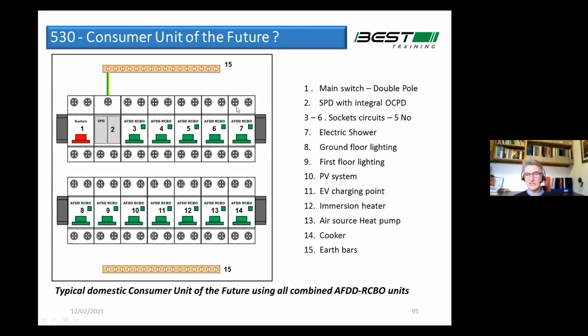Now the rest of the consumer unit here, some might say, well, that's squeaky clean, very nice consumer unit, and it is. And if I was a designer, this is what I'd be telling my client, this is the right way to go. So what I'm showing here is they're effectively RCBOs, but if you can see the text there, I have AFDD RCBO. So what I'm suggesting is that we move along, even though it's only a recommendation, I think we should move towards arc fault detection devices in consumer units. It's there to protect people's lives.